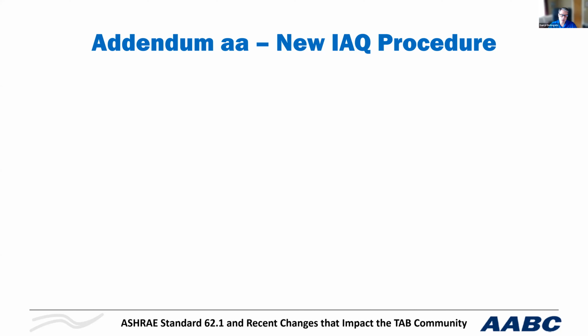as opposed to a source cancellation method, or ventilating for a specific compound that's in the air. The intent of the IAQ procedure has always been to provide the same indoor air quality that you would have with a ventilation rate procedure, but engineered a different way. Today, there are a lot more sources of chemicals. Back in 1981, there wasn't a computer on every desk. There wasn't maybe a printer on every desk. There were far less copiers. There were less products like desks and carpets and everything else. They're synthetic. They're potentially off-gassing. And people wear a lot more synthetic material clothing and sneakers and perfumes than they used to in the past. Certainly, we don't have the smoking, but there's a lot of things that you can't see.